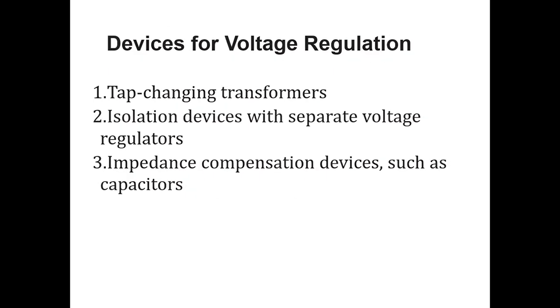Now, what are the different devices that we can use for voltage regulation? We can use tap changing transformers, which we have discussed earlier. So OLTC, that is on load tap changers, otherwise we use the off load tap changers. If you use on load tap changers, that is better, because as soon as your voltage drops, that can be sensed by that particular OLTC, and accordingly the tap of the transformer is chosen by the OLTC, and you will get voltage regulation in a proper way.